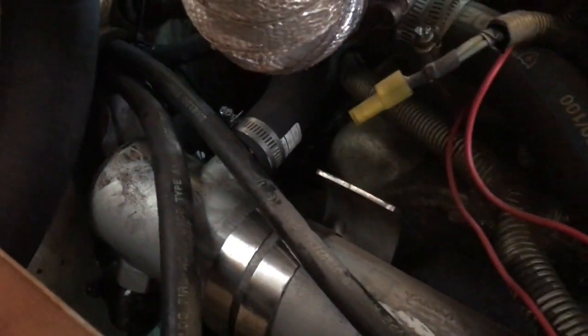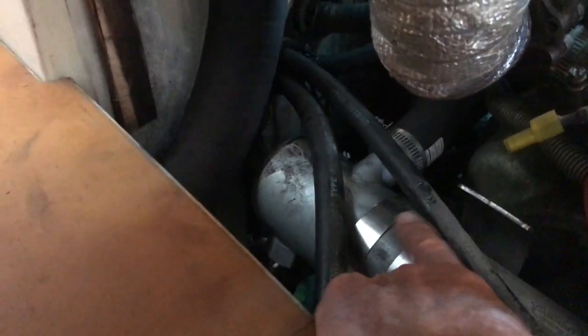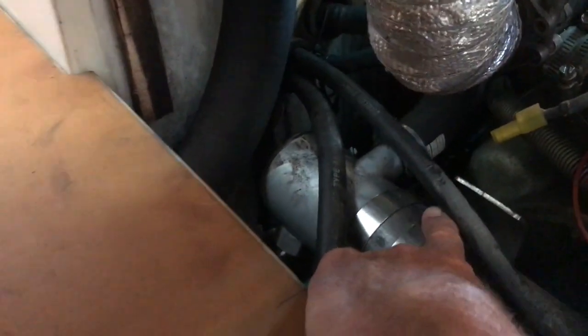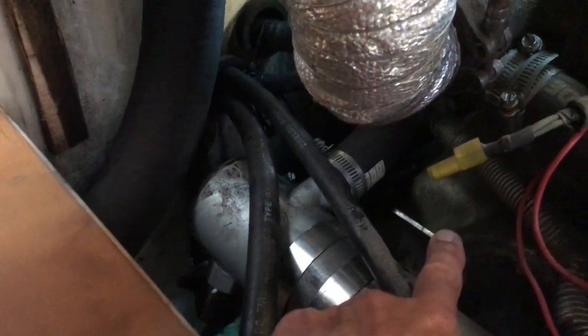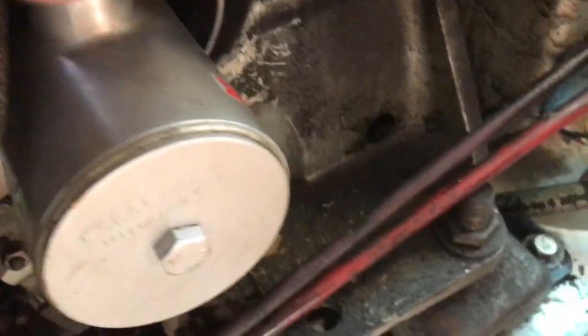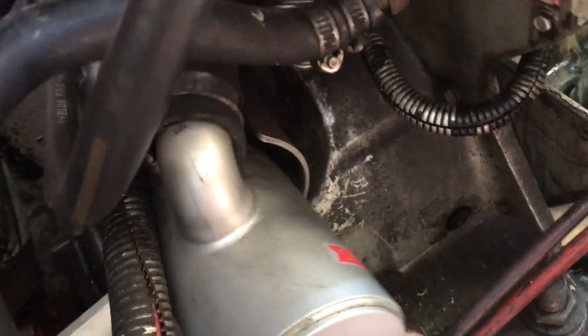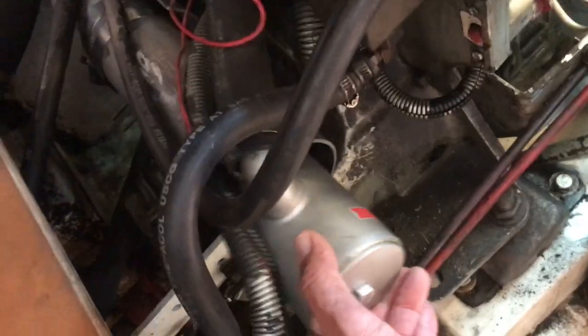Here is the existing heat exchanger. It seems to have a small leak in it. It looks like these two hose clamps which secure the heat exchanger up away from the motor have either come loose or were not installed correctly. So we're going to swap this one out, put in the new one, and make sure it's secured properly. You can see here it's moving around.